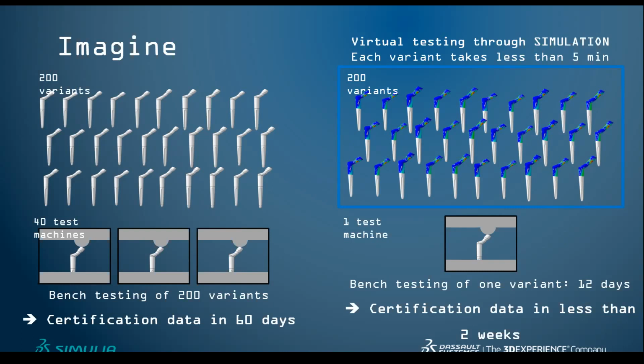And that's the other benefit: you know that, at least virtually, that particular implant has passed simulation. But you take the worst performing one and test it on a workbench, which will obviously take 12 days, and you will only need one test machine to perform that. So overall, certification can be done in less than 2 weeks. That is 12 days for that one test, plus a little bit of extra time that you need ahead of time for simulation.